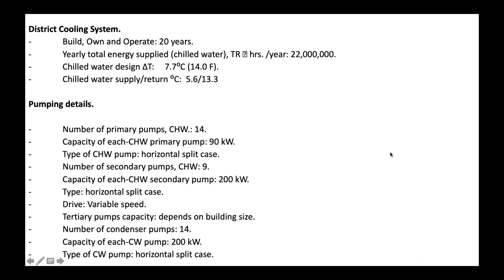The system consists of 14 primary pumps, each one 90 kilowatts, and a horizontal split case, and the 9 chilled water pumps, each one is 200 kilowatts, and all pumps are variable speed. Next one, please.